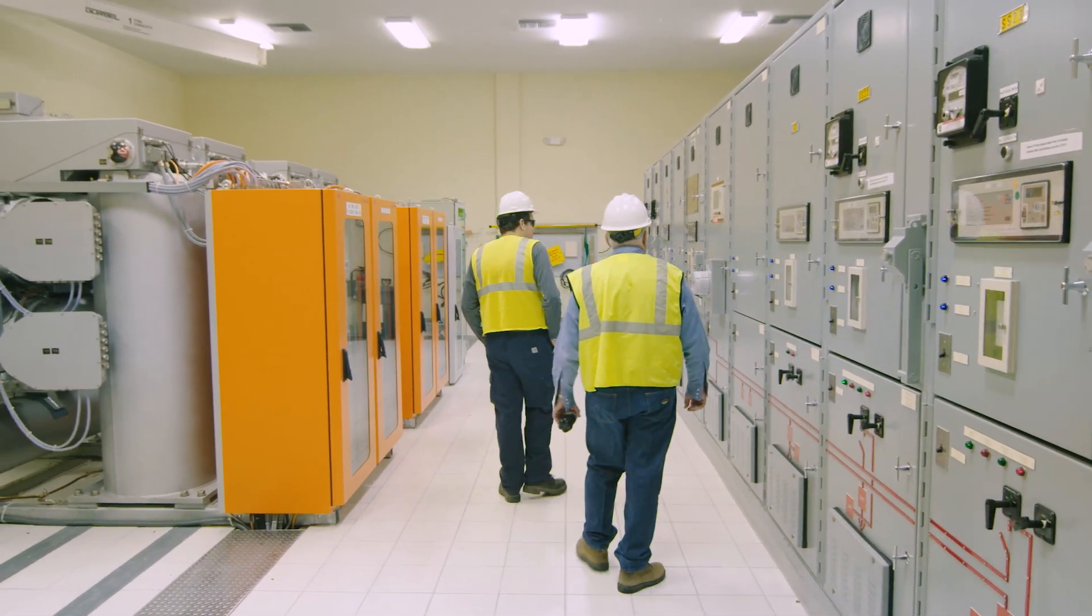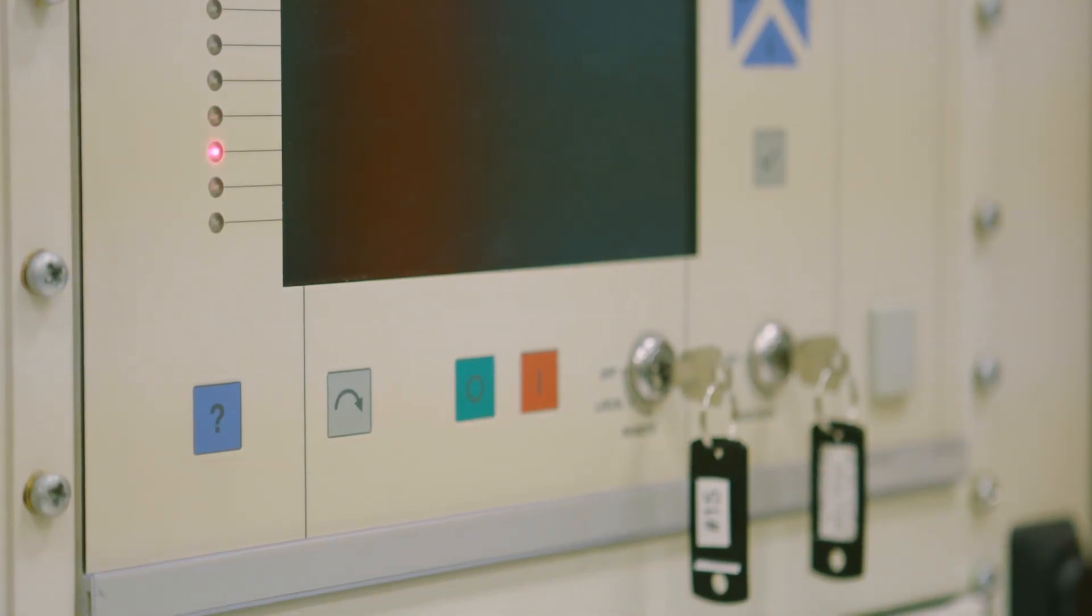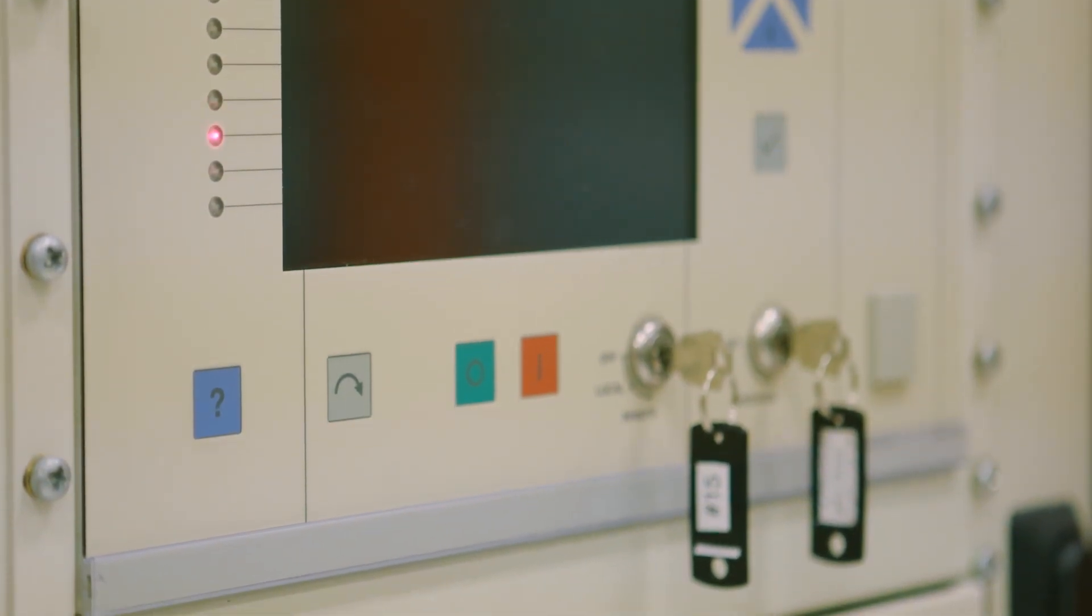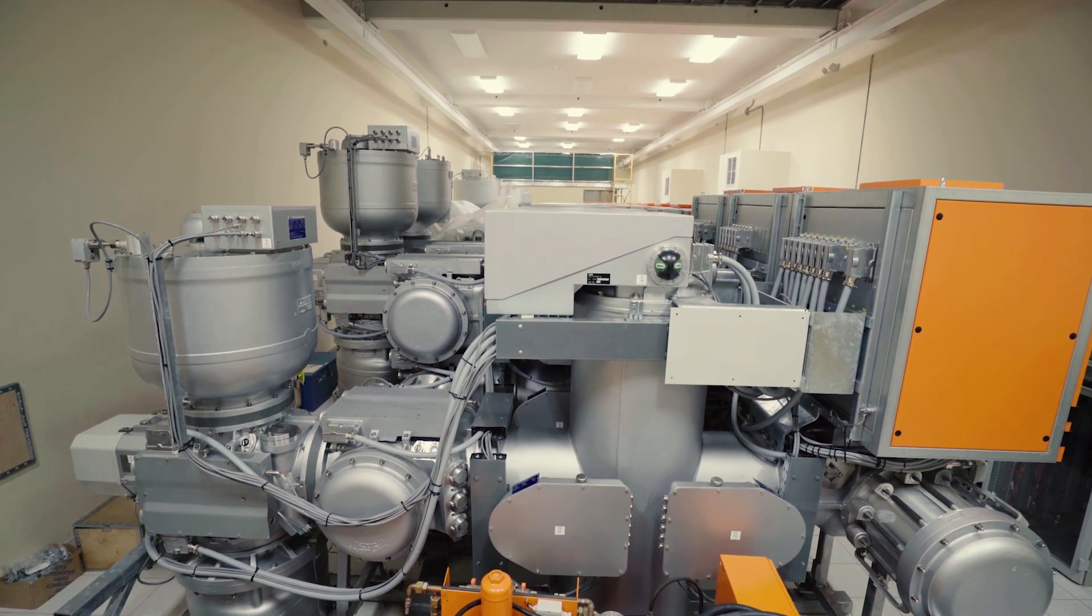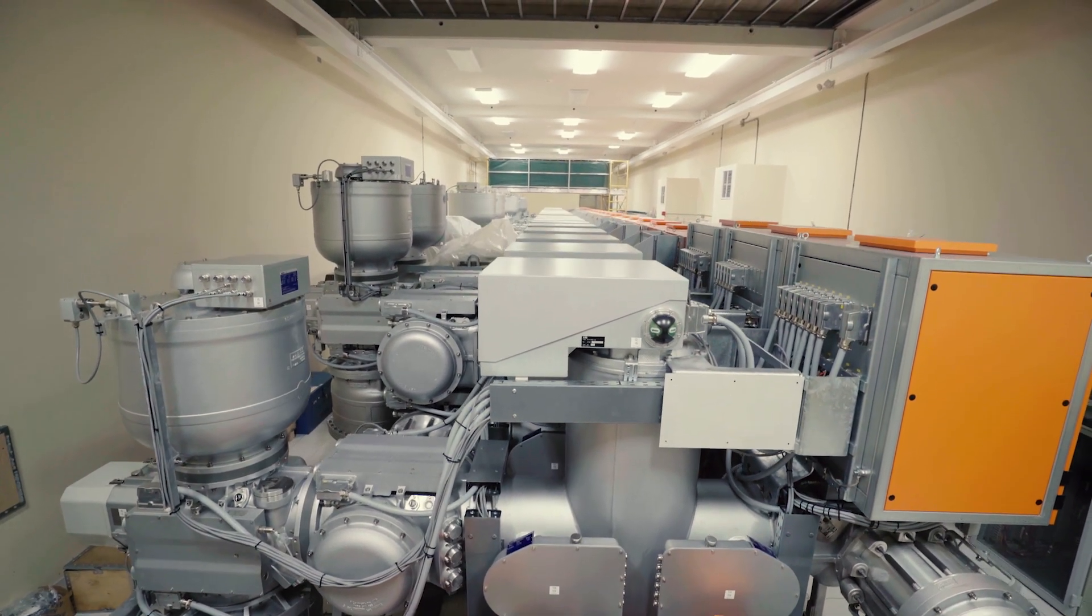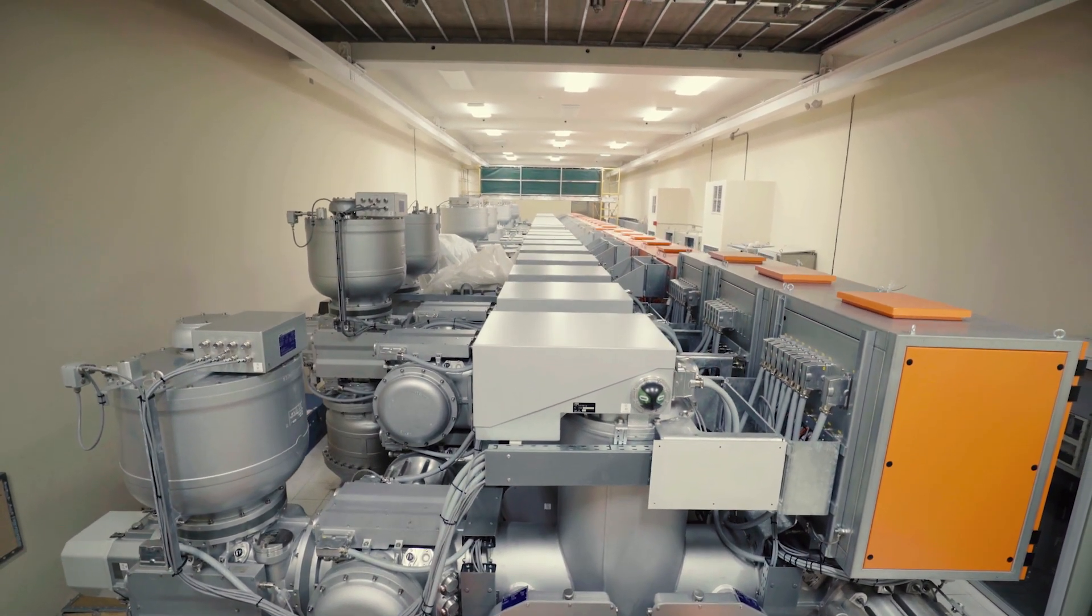The bay controllers that send control signals to breakers, earth switches, that kind of thing, the supplier deemed them obsolete and they weren't willing to support them anymore. So that left us in a vulnerable position. The systems were failing. The hardware, the power supplies were failing and they're running out of spares because it's obsolete. They can't get new parts anymore.